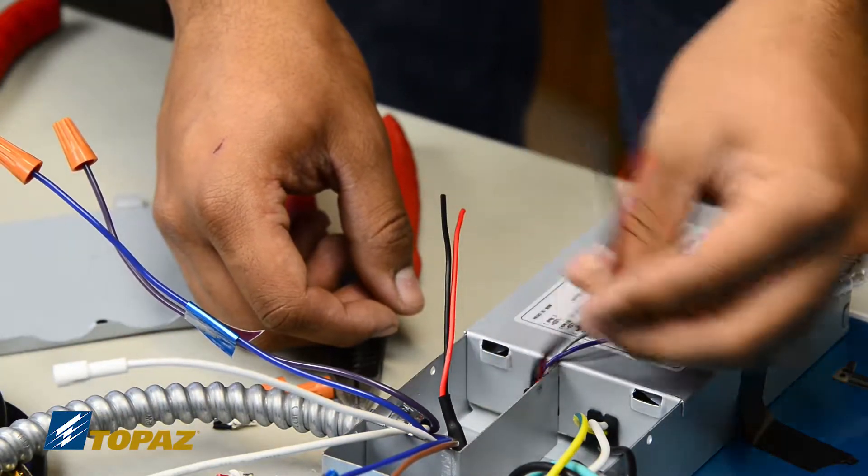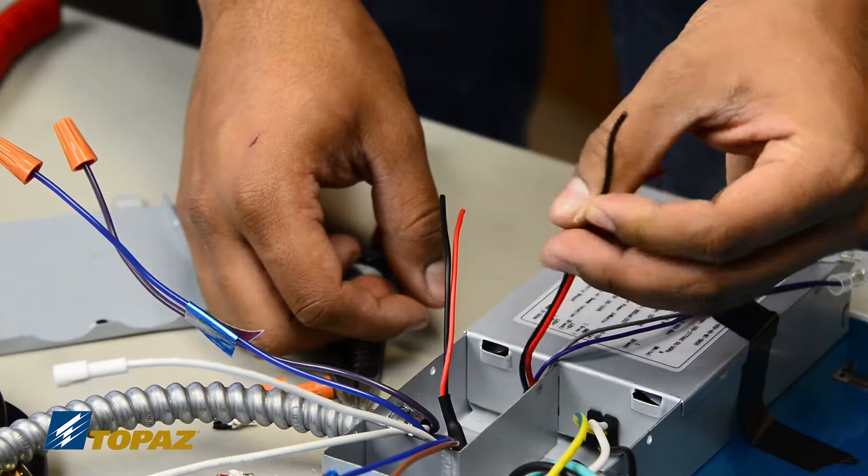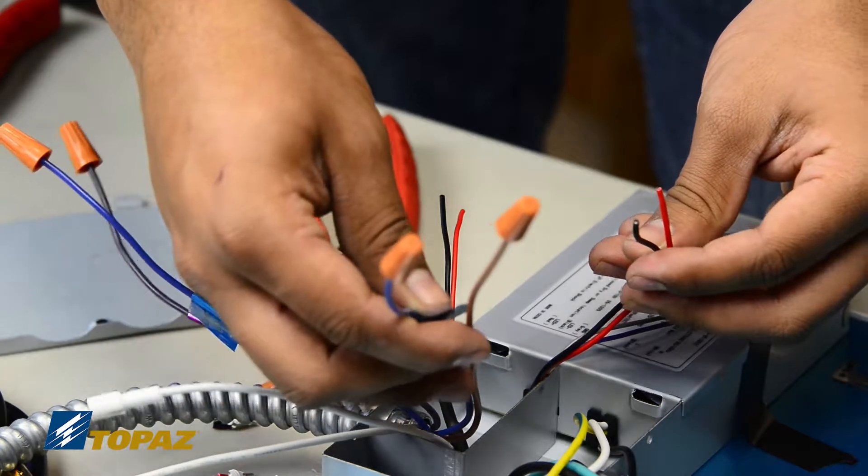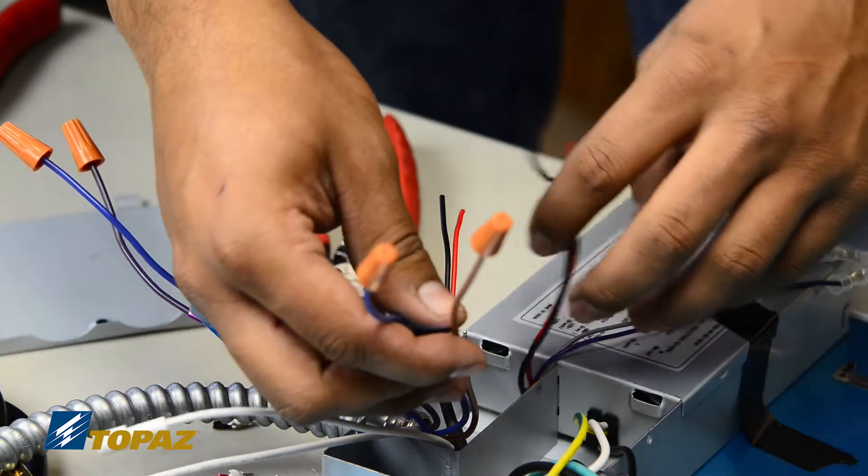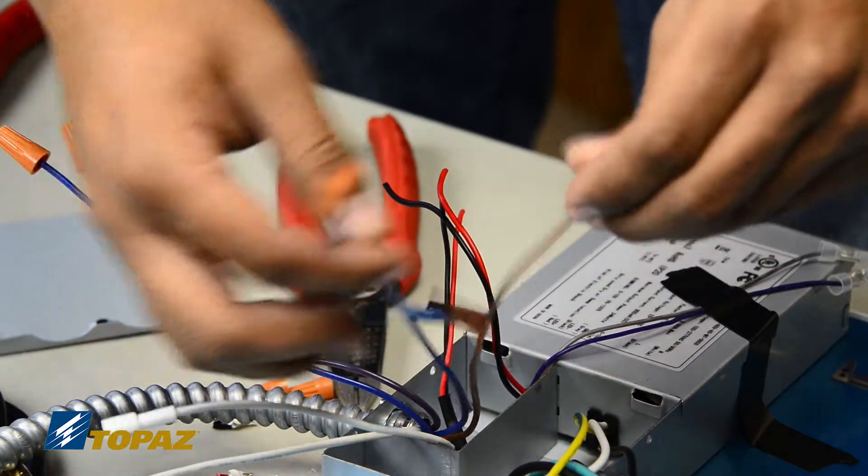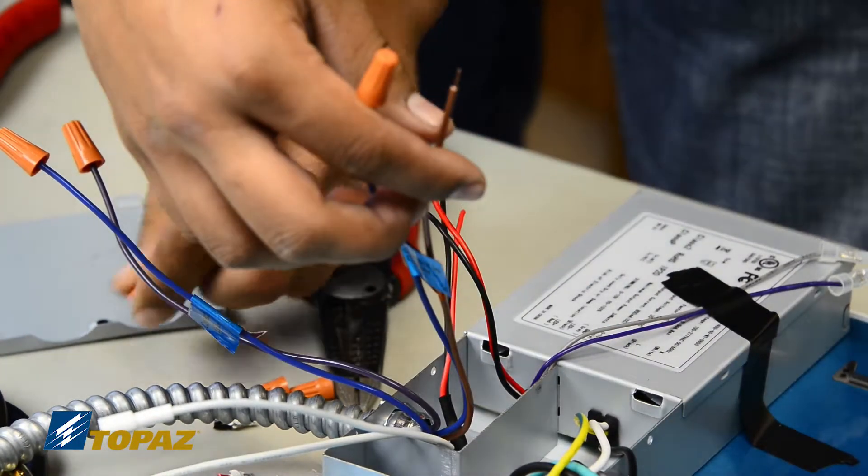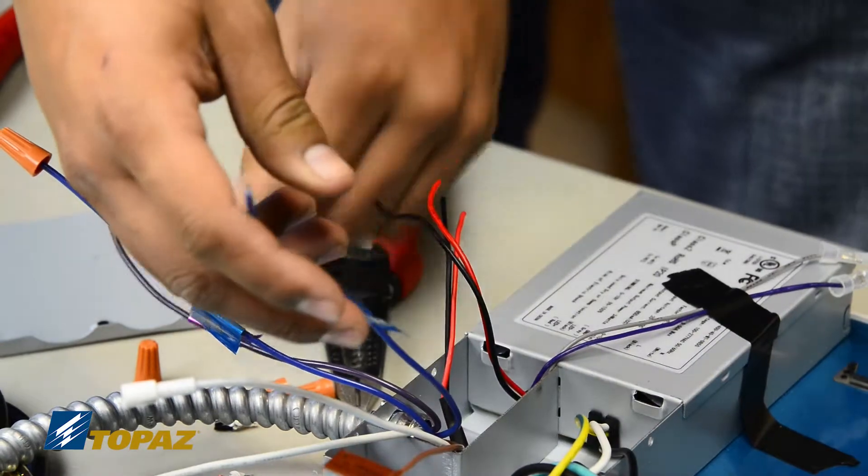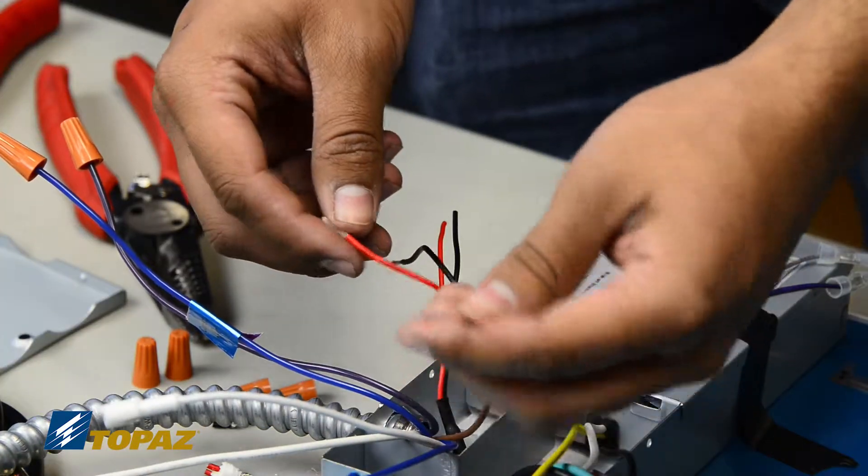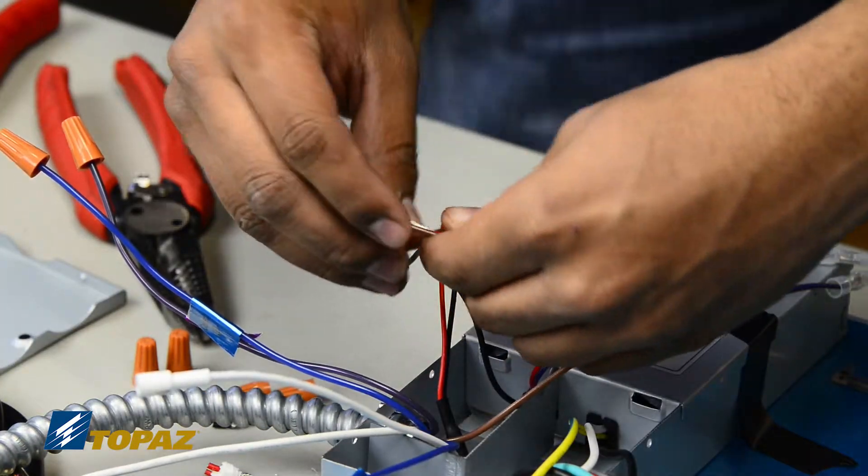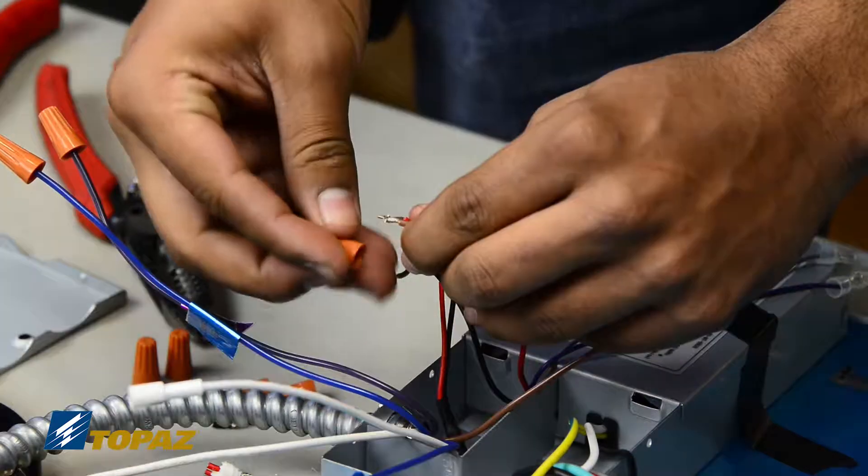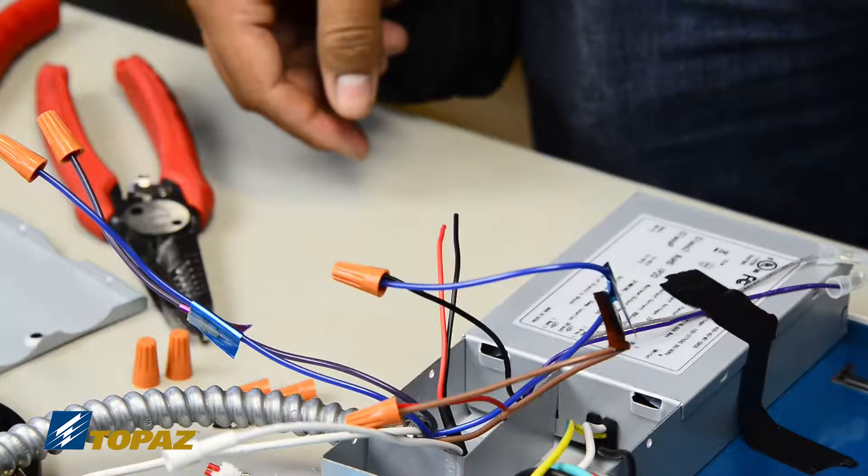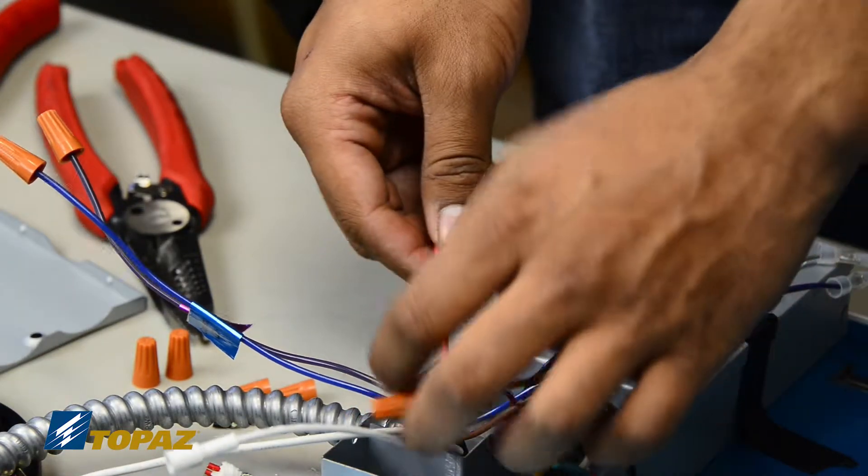We'll start with the LED driver leads, the black and red. We're going to now pair it up with the tags that came with the backup ballast. You'll notice that the tags are identified as LED driver with a positive and a negative marking. Red will be going to the positive and black will be going to your negative. We're going to connect the positive lead first, now we do the negative lead.